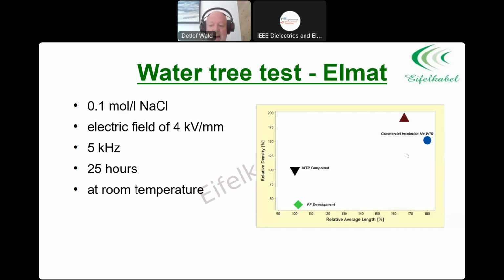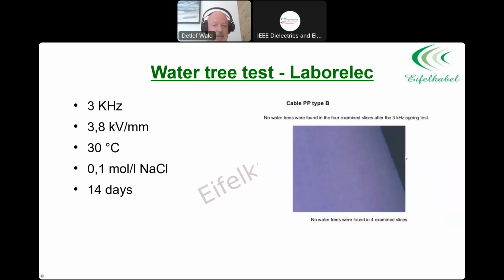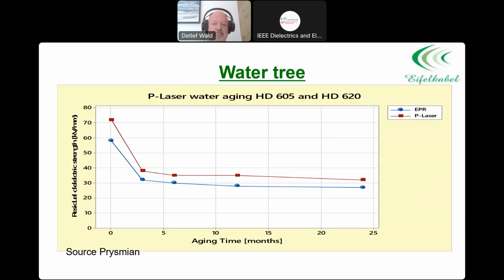Commercial compounds are up here. Cable tests have been done at Laborelec, which is the test house in Belgium, and they couldn't find any water trees in that test. Also, like I said, the leader is Prysmian. When doing a 2-year test according to the harmonized CENELEC European specification, harmonized documents HD 605 and HD 620, they compared EPR with polypropylene. It has the same water tree behavior on a cable as an EPR in that specific test.